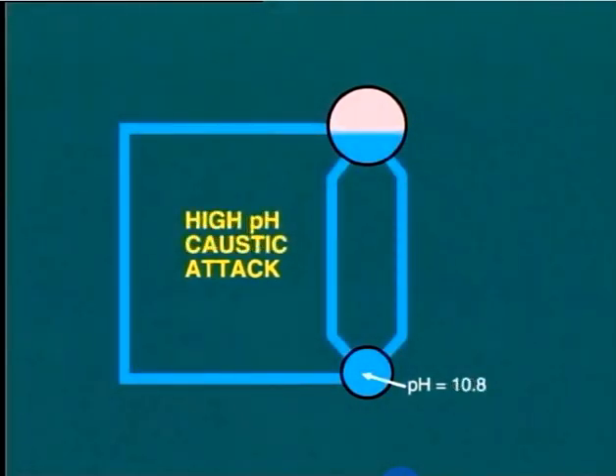Caustic attack, which occurs when the alkalinity of the boiler water is too high. The pH level is above about 10.5.